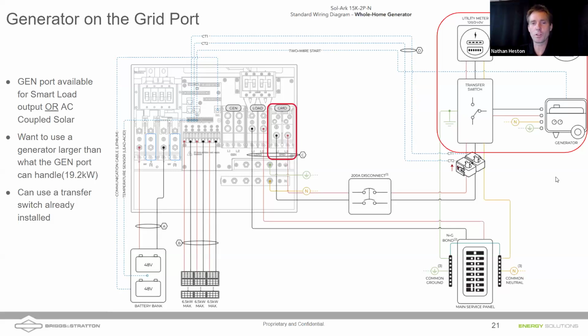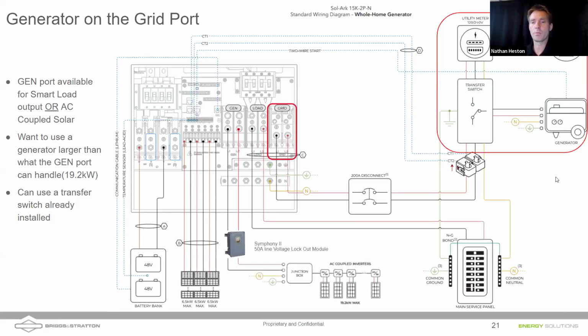So I was going to ask you, Daniel, what could you use that gen port for? And I know you've got some notes on the screen. You could use it for AC solar, or you could use that generator port as a smart loads port for some loads you might want to turn off in a grid outage. So if we have AC coupled solar on there, we can do something else more clever. And what are we looking at, Daniel? So again, what we want is the ability for that AC coupled solar to shut itself off, right? The Sol-Ark wants to use frequency shifting to curtail the charge of that AC coupled solar. If we add a generator, that functionality is lost.